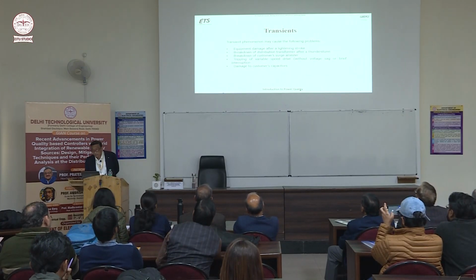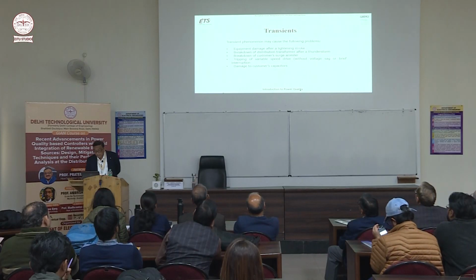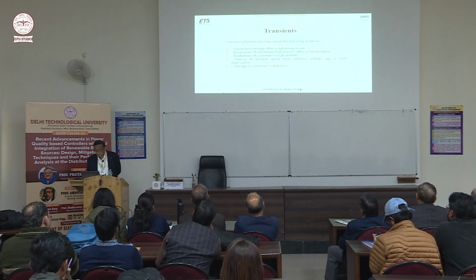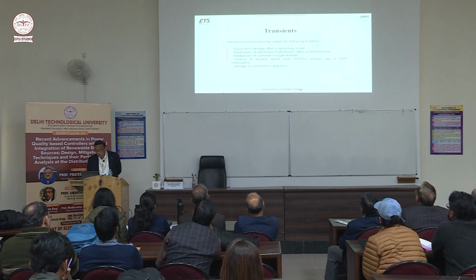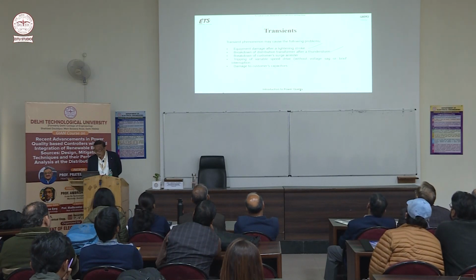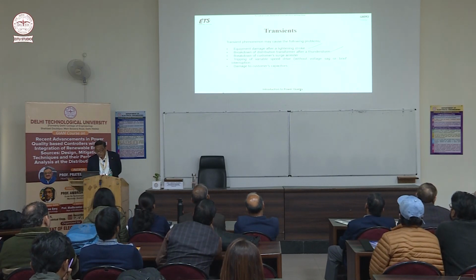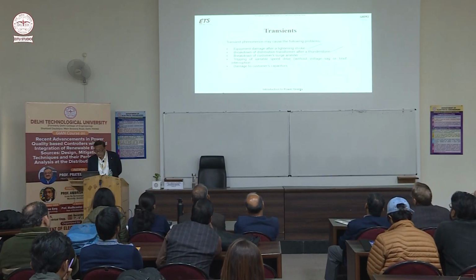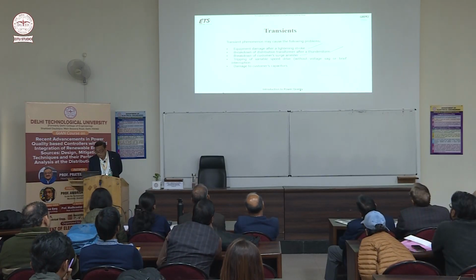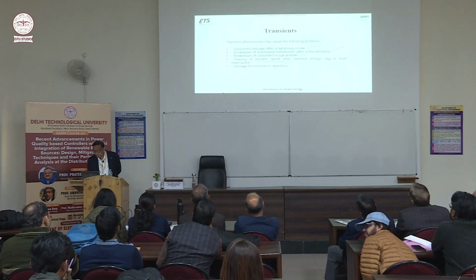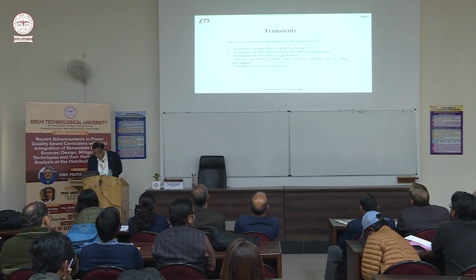Transient phenomena may cause the following problems: equipment damage after the lightning stroke, breakdown of distribution transformer after thunderstorm, breakdown of customer's surge arrestor, tripping of variable speed drive without voltage sag or brief interruption, damage to customers' capacitors.